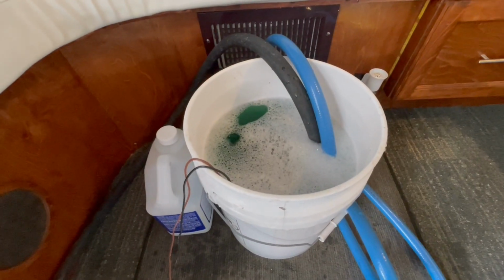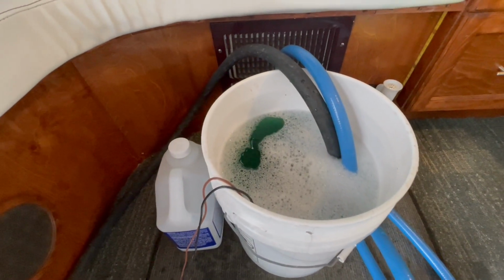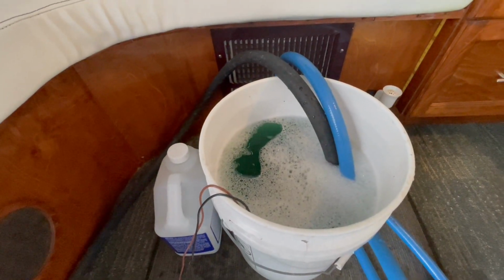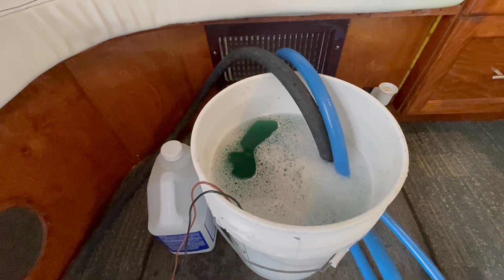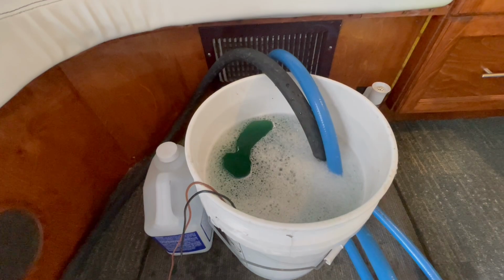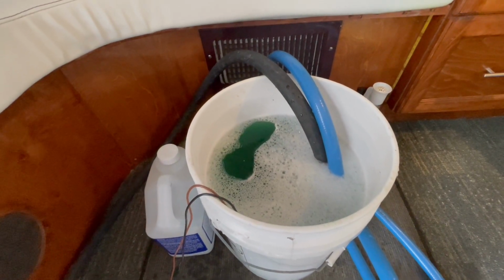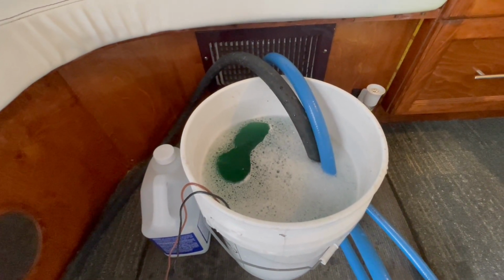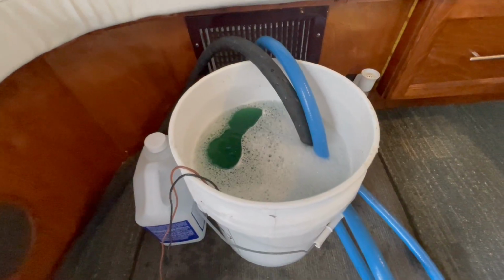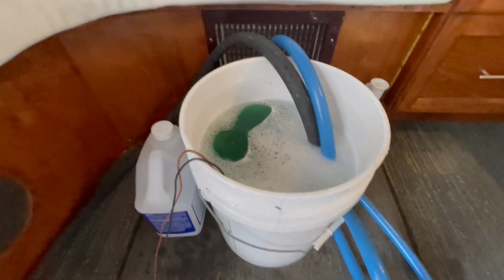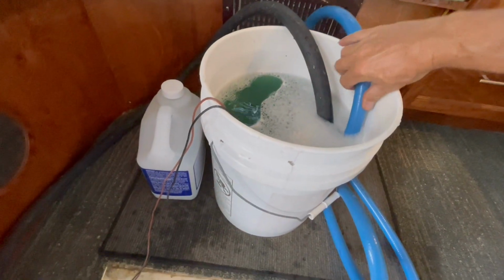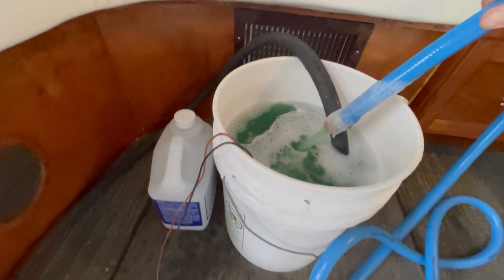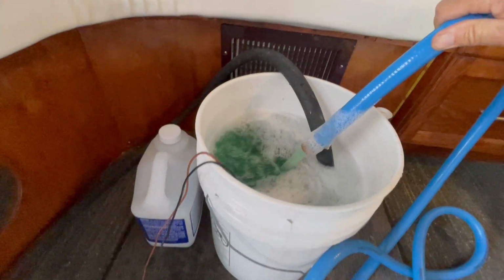So I've added my acid and it's circulating. You'll notice the foam, that's the acid doing its thing, working on the debris and stuff. You want to pump it until that quits for sure. Make sure your discharge hose is down below the surface. If you don't, it makes bubbles too, but you'll notice there it is returning.